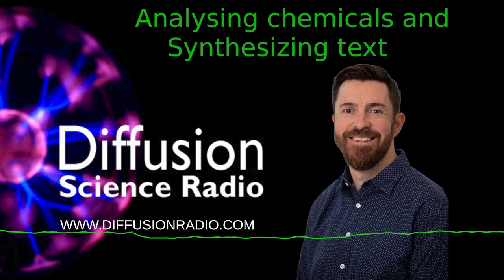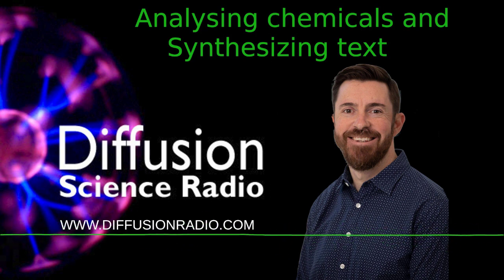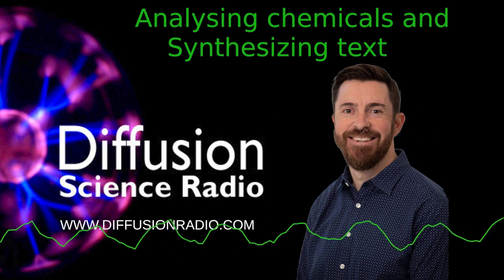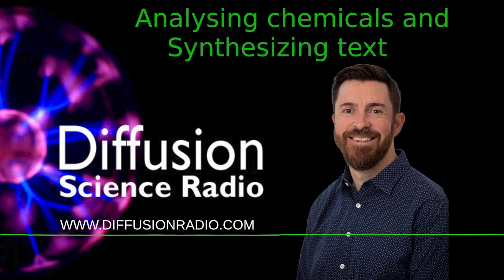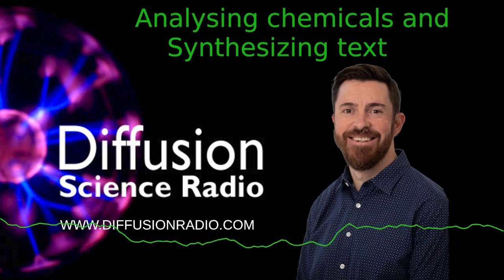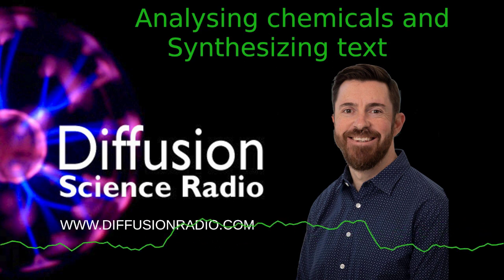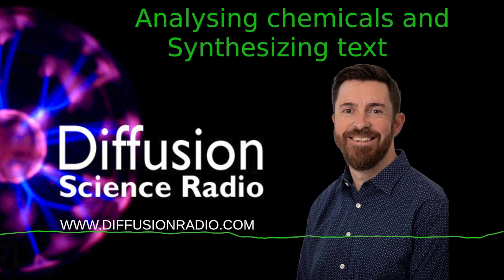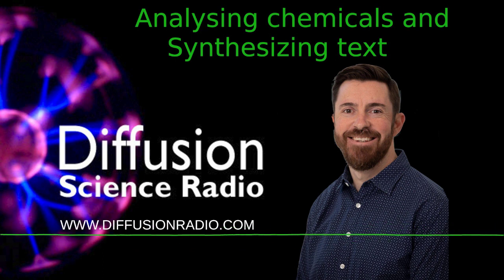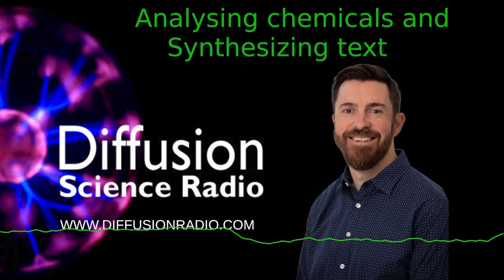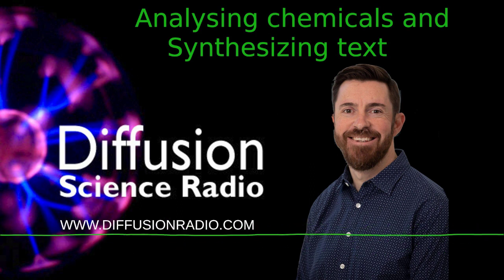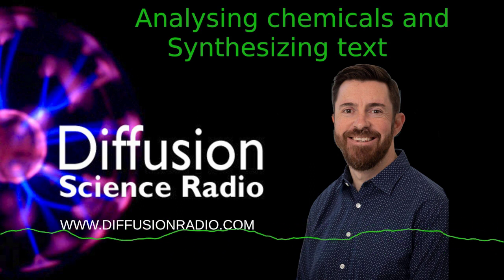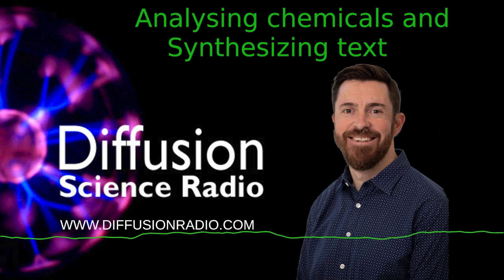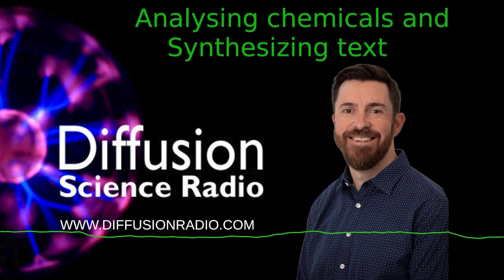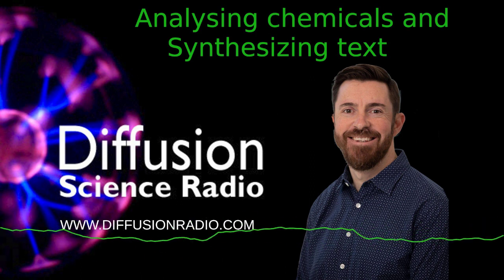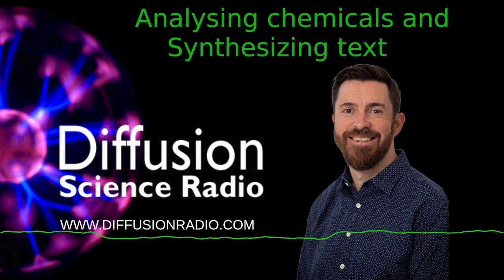Now, the plasma is a very hot ionized gas. In this case, we have an argon-based plasma, and it's about as hot as the surface of the sun. As our nebulized solution goes into this plasma, it first off desolvates, so it gets rid of all the excess water surrounding our metals of interest. And after desolvation, there's excess energy from the plasma which will ionize the atoms of the metals going through. And once it's atomized and ionized, it is then capable of entering into the mass spectrometer. So the plasma has an excess of electrons in it, which will allow ionization of the atoms to occur.